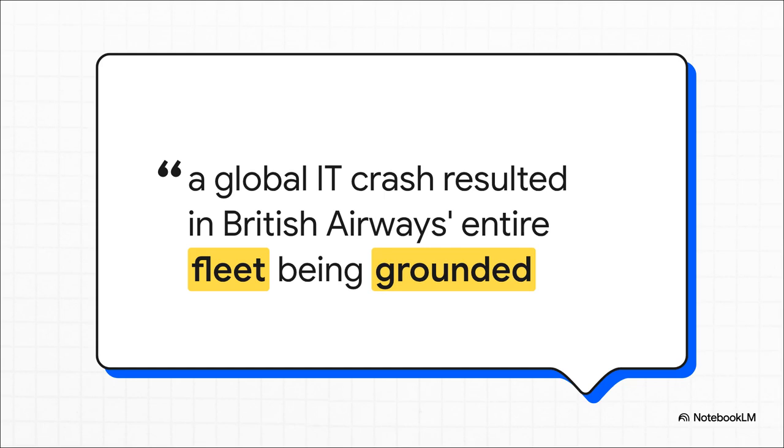And it's not always some incredibly complex, systemic failure either. Sometimes it's a completely mundane, almost silly physical mistake. Take British Airways in 2017. A power supply was accidentally switched off. That one human error sparked a global IT crash, grounded their entire fleet, and stranded thousands of passengers during a massively busy UK holiday weekend, just from a switched-off UPS.